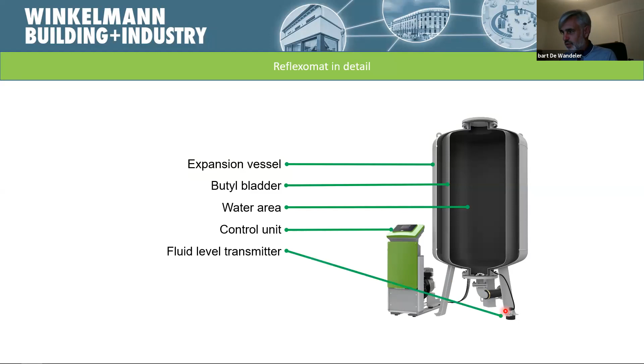This is also a critical part, below the vessel - the pressure unit or pressure load cell that makes sure we know how much water is in the vessel. For example, when we achieve the maximum water level as a critical point, or when we've done degassing and don't have enough water reserve, this load cell will activate all settings and alarms to ensure your system can provide extra water reserve.